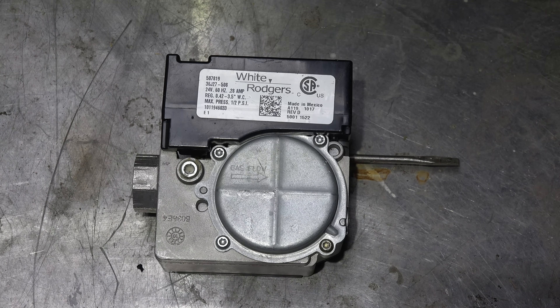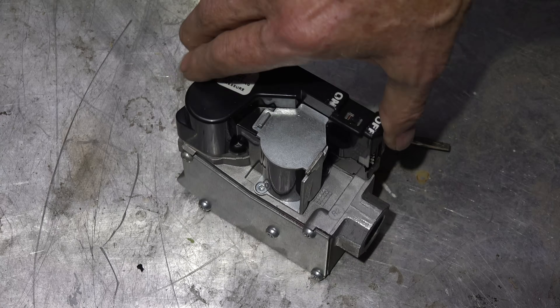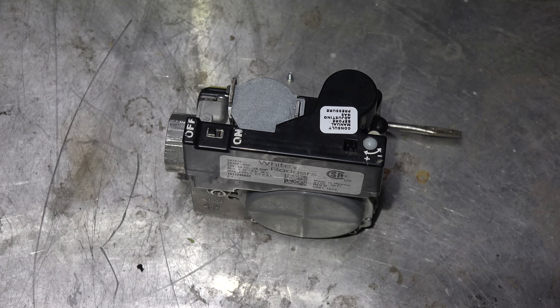In this one we're going to look at this gas valve — a White Rodgers 36J27-508. What is different about this valve over a lot of others is that it's a variable firing rate valve, continuously variable from about 35 percent to 100 percent. This certainly isn't a new valve; they've been around for quite a while, but the interesting part is the variable firing rate and we're going to figure out how that works.